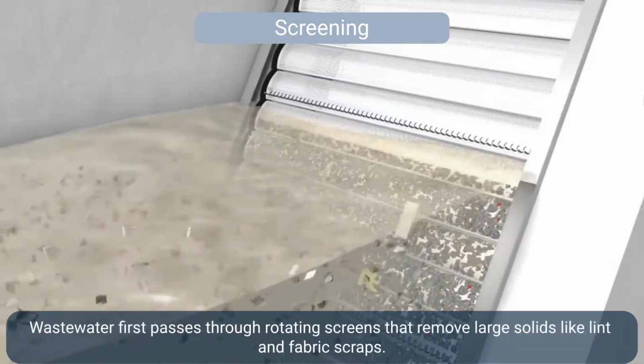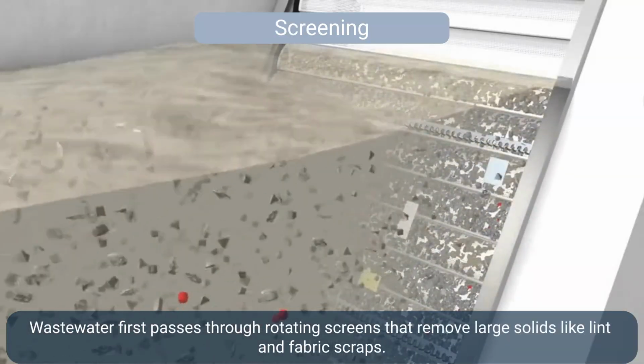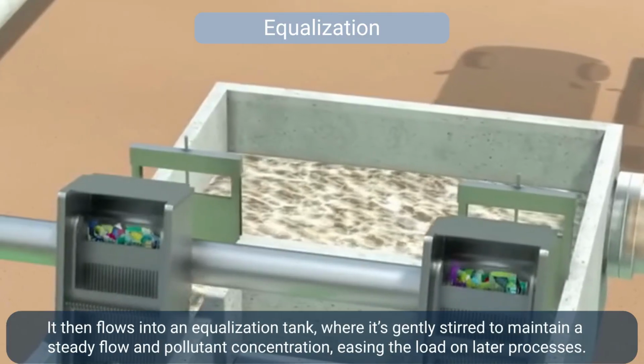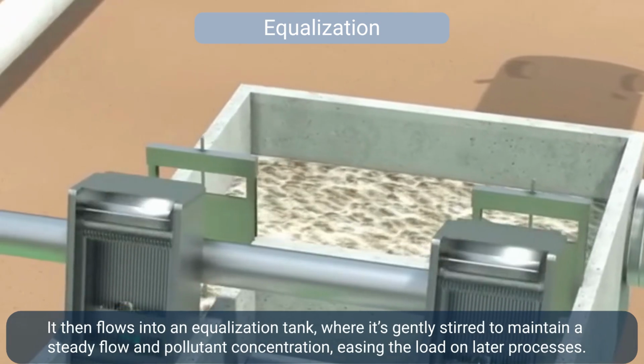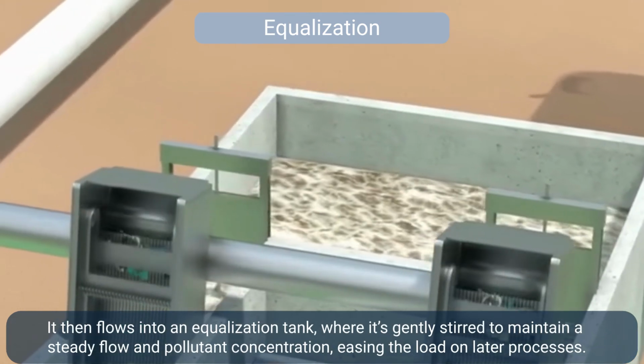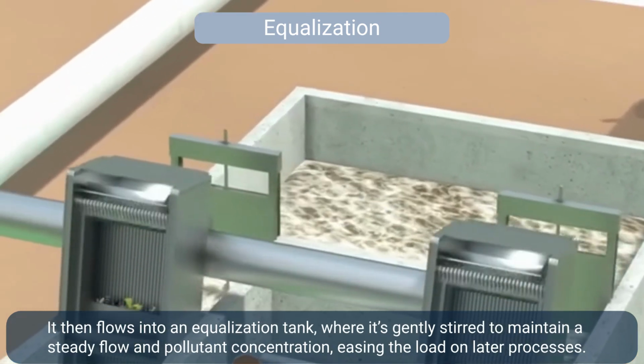Wastewater first passes through rotating screens that remove large solids like lint and fabric scraps. It then flows into an equalization tank where it's gently stirred to maintain a steady flow and pollutant concentration, easing the load on later processes.